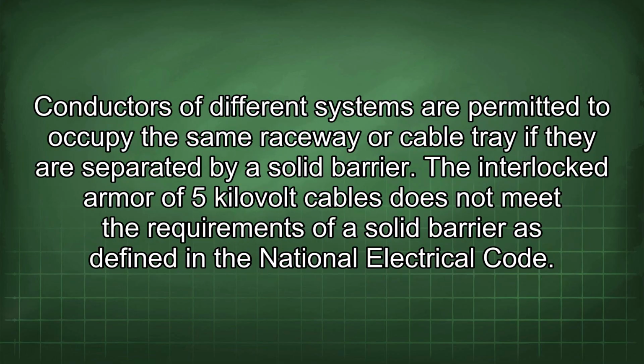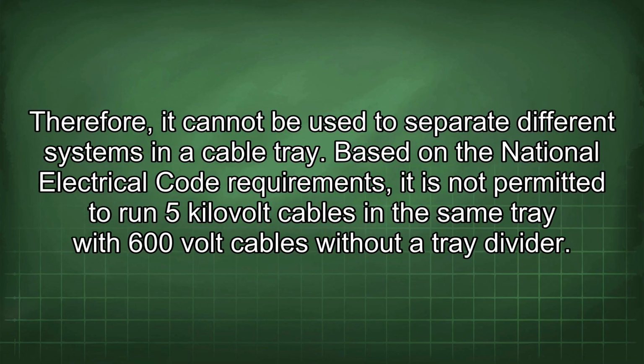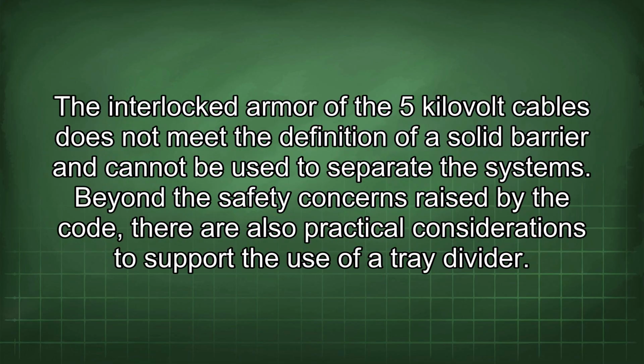Conductors of different systems are permitted to occupy the same raceway or cable tray if they are separated by a solid barrier. The interlocked armor of 5 kilovolt cables does not meet the requirements of a solid barrier as defined in the National Electrical Code. Therefore, it cannot be used to separate different systems in a cable tray. Based on the National Electrical Code requirements, it is not permitted to run 5 kilovolt cables in the same tray with 600 volt cables without a tray divider. The interlocked armor of the 5 kilovolt cables does not meet the definition of a solid barrier and cannot be used to separate the systems.